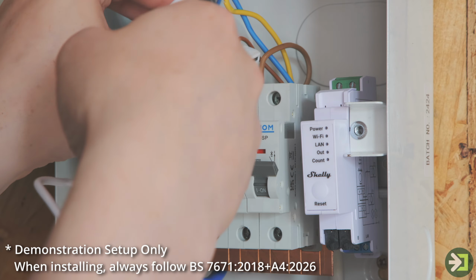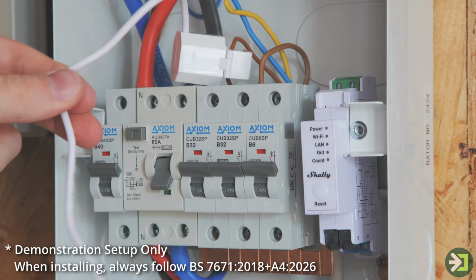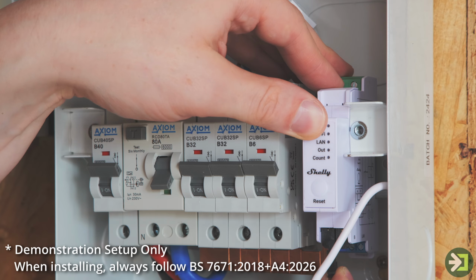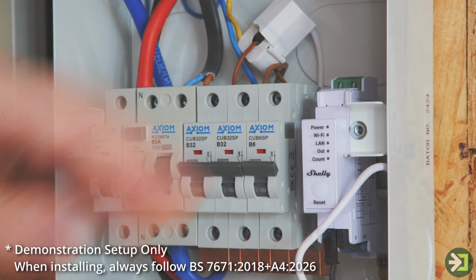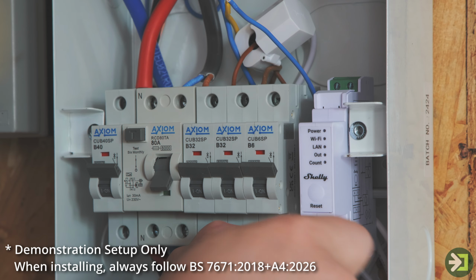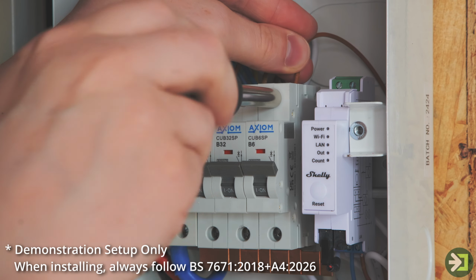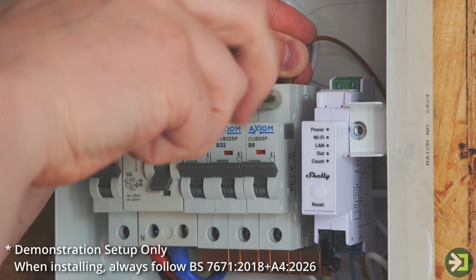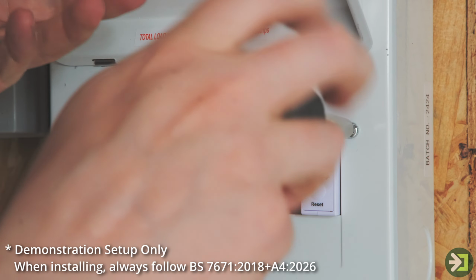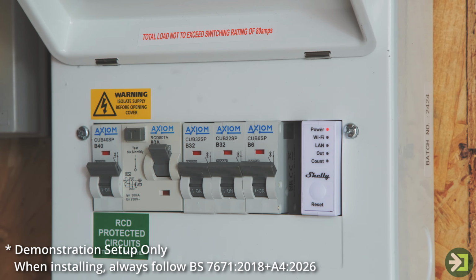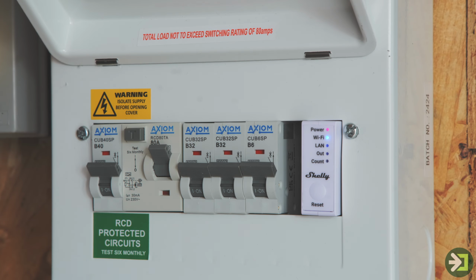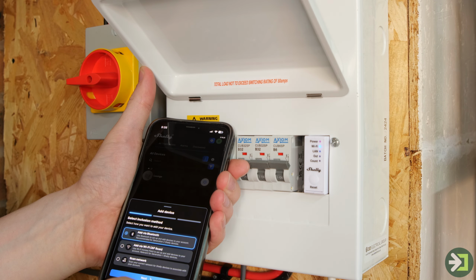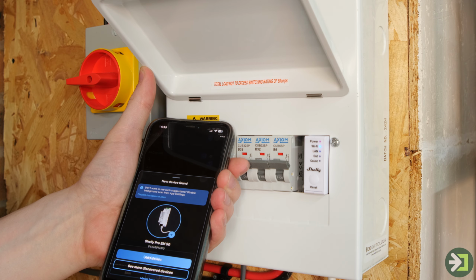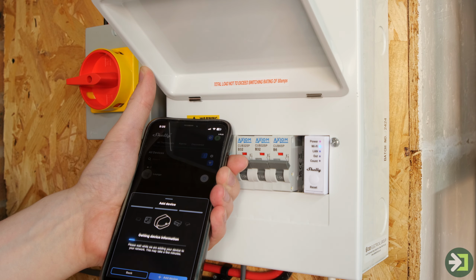The current transformer clamps are placed around the relevant conductors, and the device handles measurement and reporting internally. Because the measurement is done via current transformers, there is no need to break circuits or reroute loads through the device itself. This makes it ideal for professional installations where safety, compliance, and maintenance capability matter. The integrated relay can then be used to trigger a contactor if load control is required, allowing the system to scale far beyond the onboard current rating.